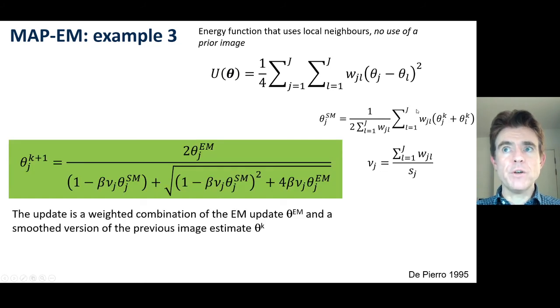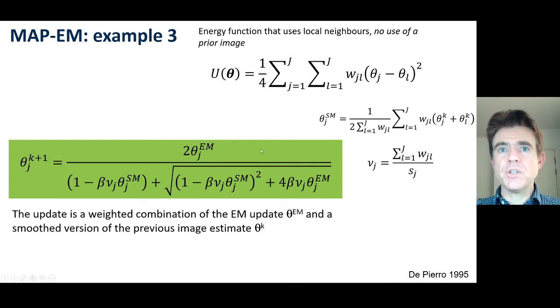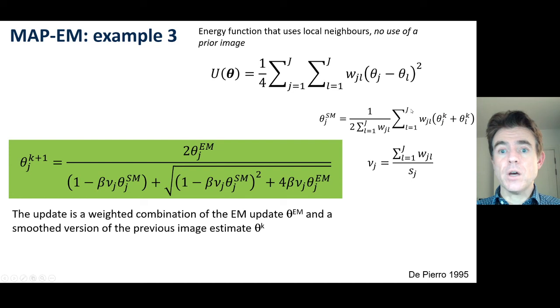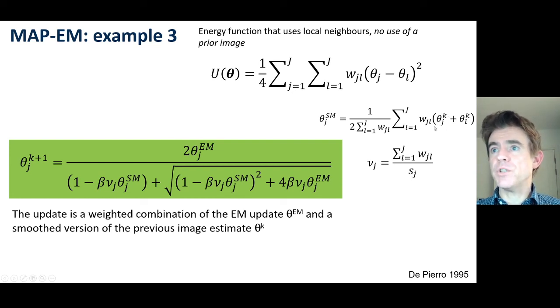De Pierro found a very clever way of building that into the MAP framework. The resulting expression is very similar to the prior image formulation, except instead of using some prior image, we use a smoothed update of the current estimate — and that accounts for the weighted quadratic prior in the MAP objective.